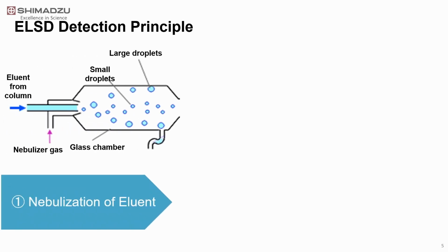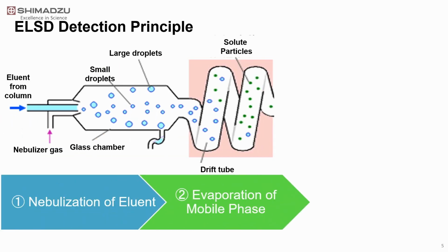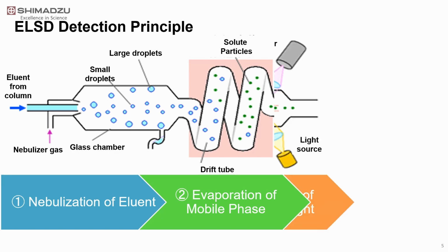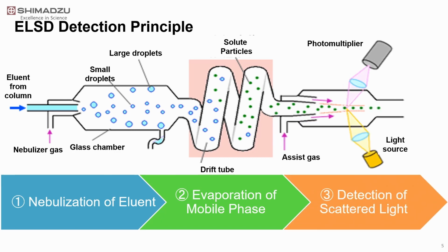ELSD detection is accomplished in three steps. First is nebulization of the eluent to inject a fine mist of mobile phase into the drift tube. Then, the ELSD can efficiently evaporate the mobile phase in the second step, even at low temperature. Shimadzu ELSD LT3 also includes a mechanism for focusing samples at the detection point with assist gas, achieving higher sensitivity.